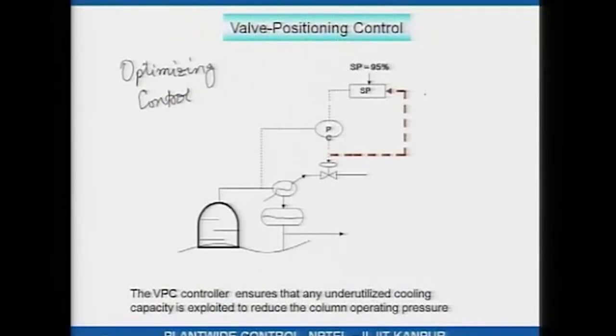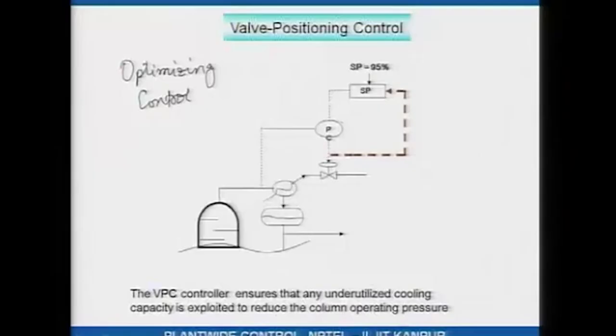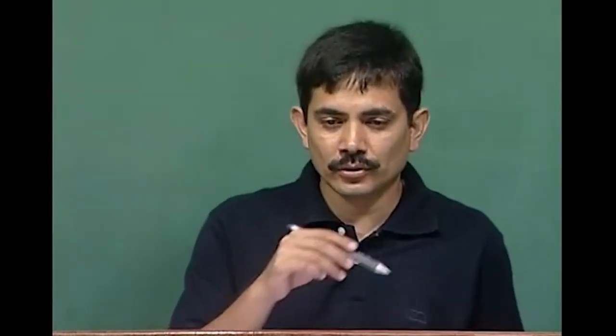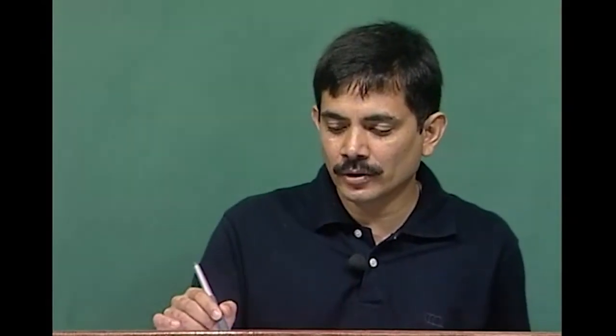Getting back to the floating pressure example: you will notice the pressure of the column will float. On hotter days, the minimum achievable operating pressure would be higher; on cooler nights, the column loses more heat and the operating pressure would be slightly lower. So if you look at the diurnal cycle, you will see that the pressure set point follows the diurnal cycle — pressure increases during the day and decreases at night.